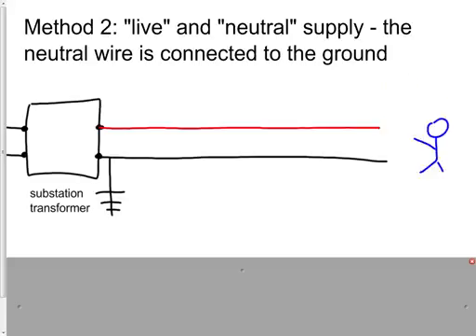So this just removes the uncertainty that existed in the isolated situation. Now we know what's what. If some of the insulation on the neutral wire gets damaged and it gets connected to the ground somewhere, it's no big issue, since it was already connected to the ground elsewhere anyway.